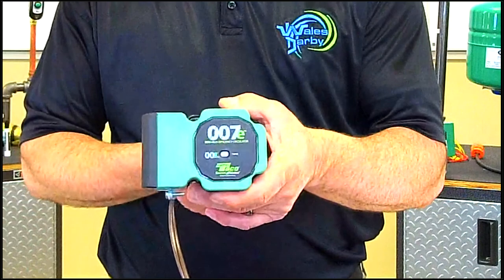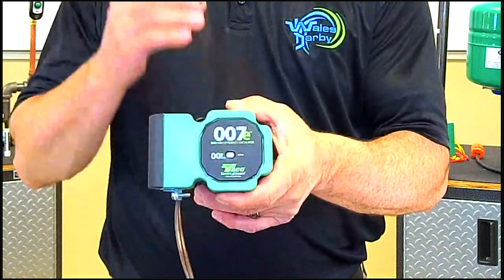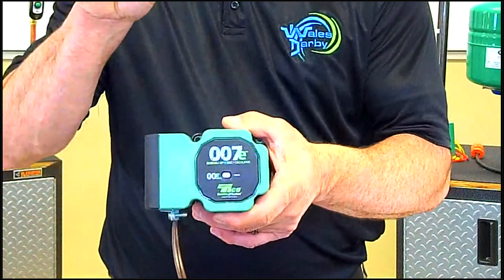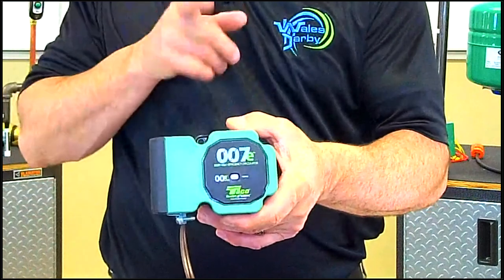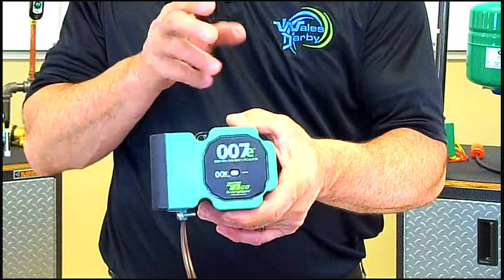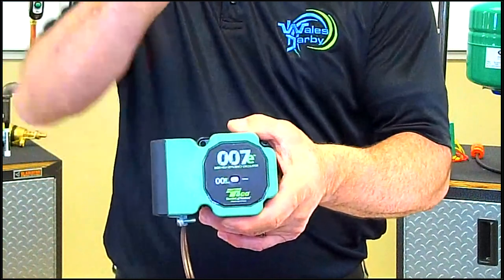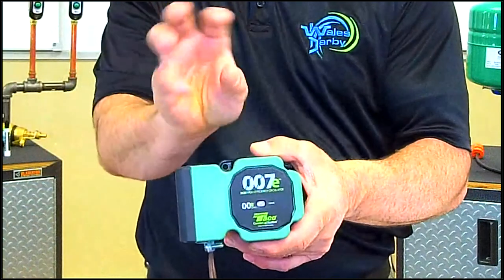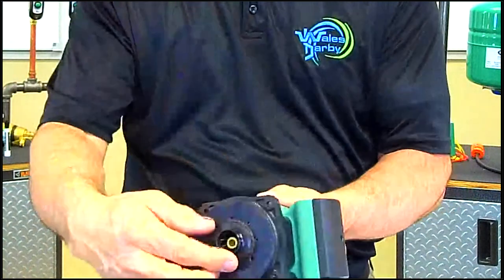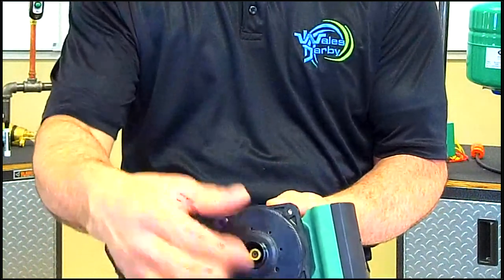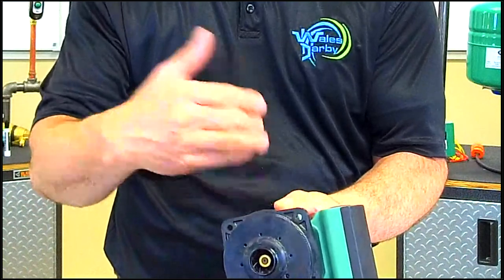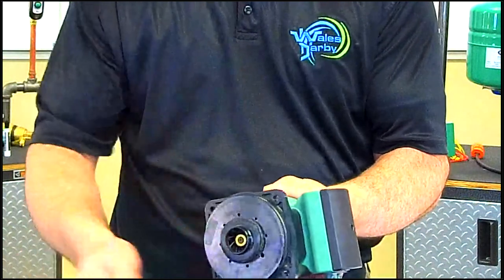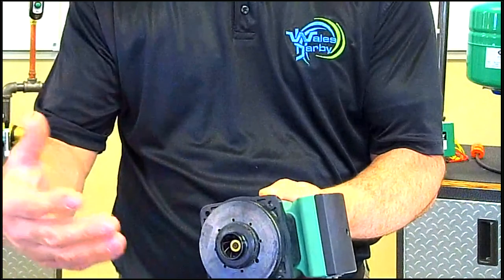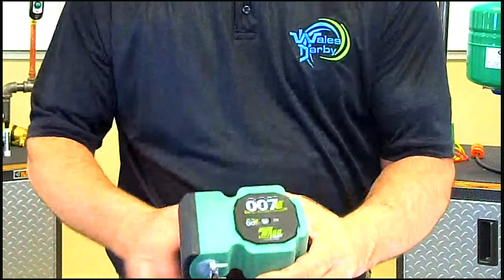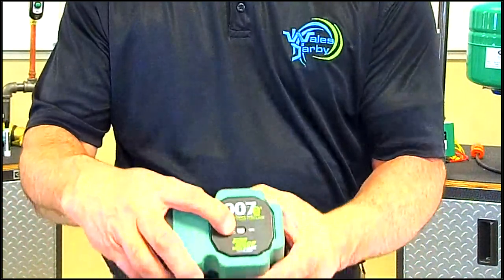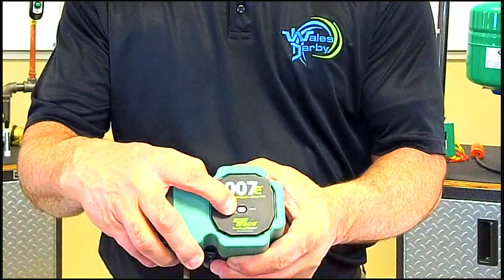The other function that this has built in is if it were stuck, it knows when it's supposed to be rotating. But if it wasn't rotating, it has the ability to rotate back and forth, back and forth, and shake the impeller to try to break loose any debris on the inside of the circulator that might be seizing it up. So each time it does that, this LED light will flash white.